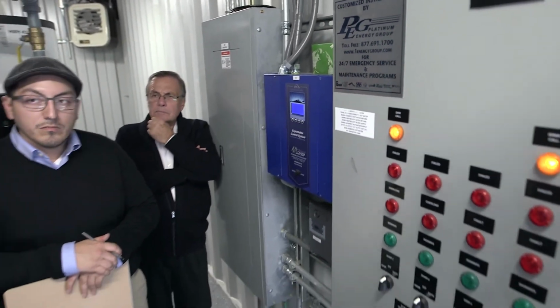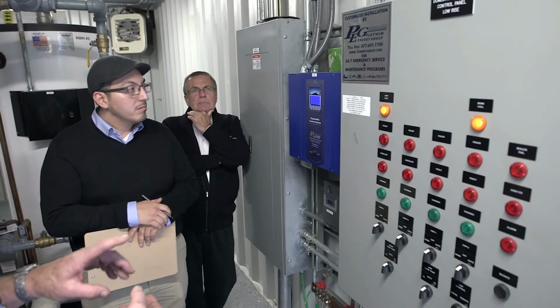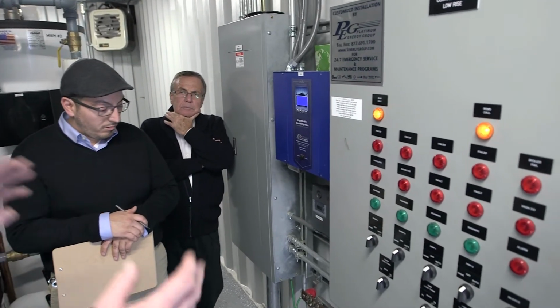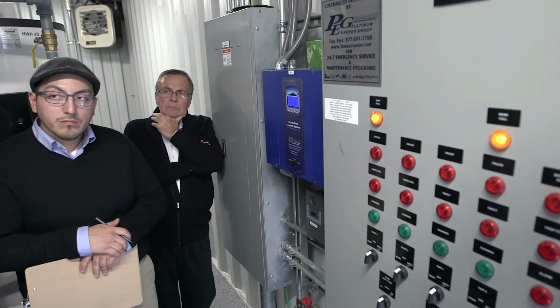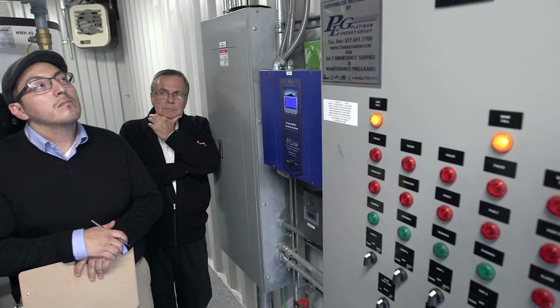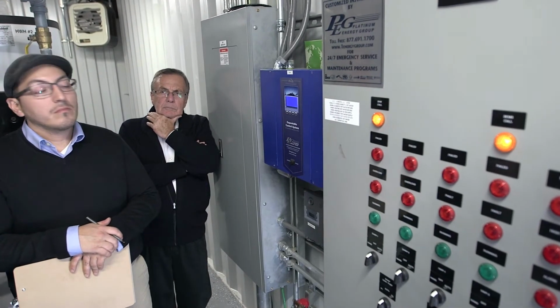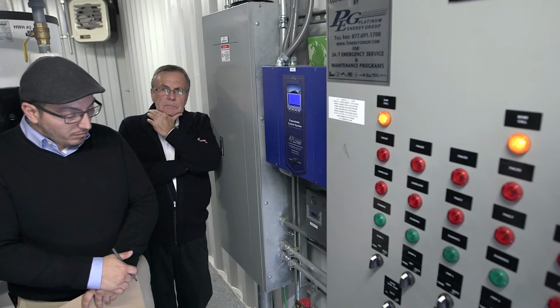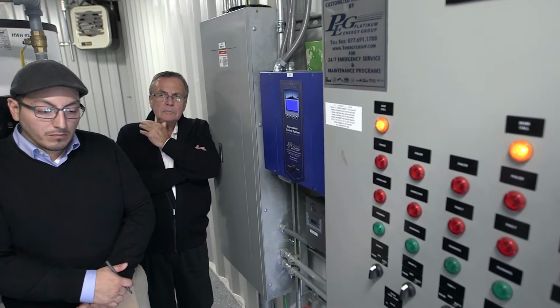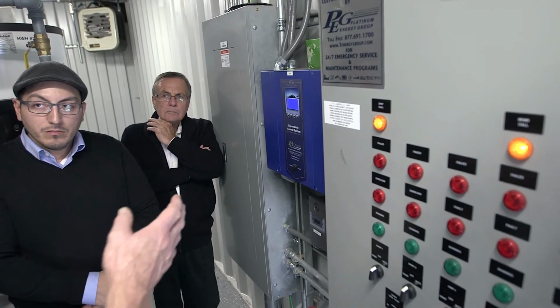It tells you what the temperature is of the supply, the return, the hot water, the stack temperature, what the temperature is in the boiler room itself, what the temperature is outside. That's what it's doing, it's monitoring. It's going to tell you the temperature in all the apartments. You have sensors in all the apartments. That's how it works.